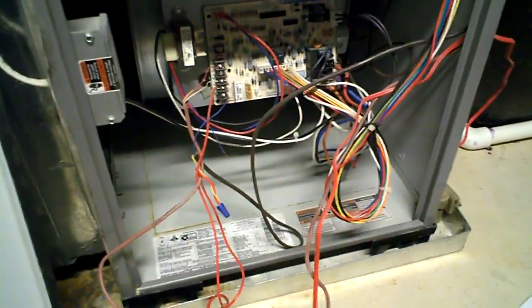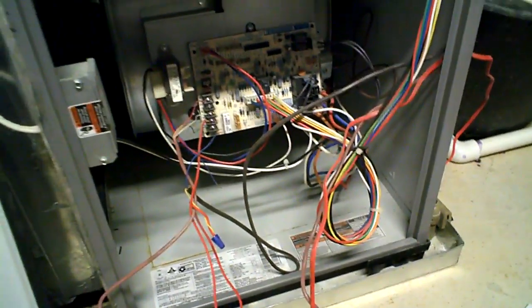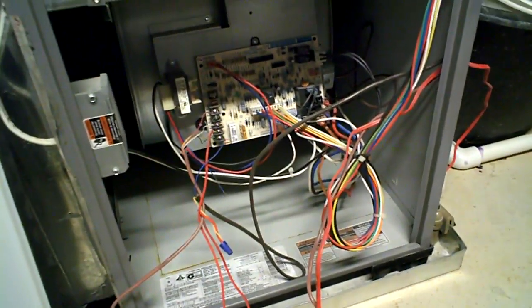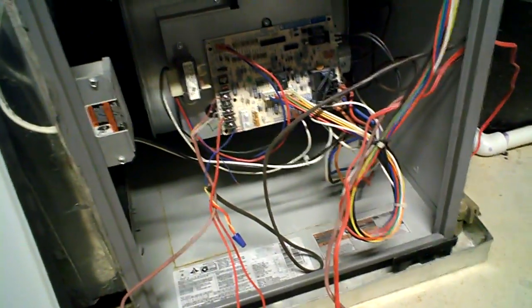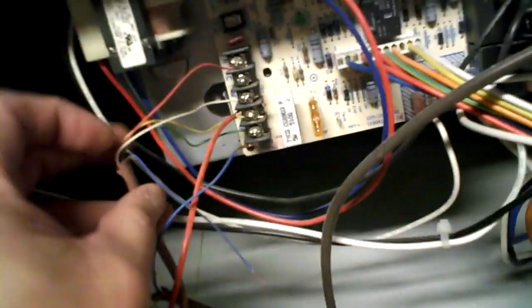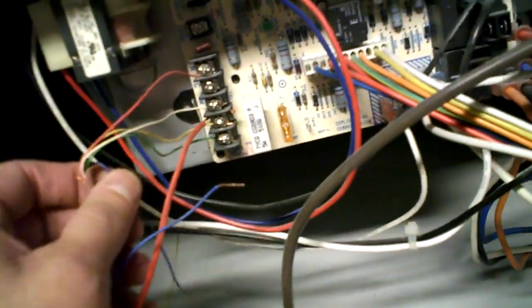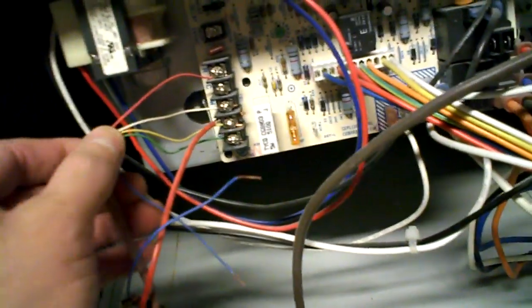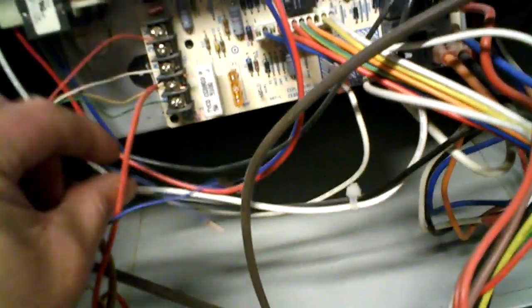Okay, I've discovered something on my system, since it's a very new system, about 3 years old, that may be of interest to people. In fact, it changes everything, because I'm not going to be installing this power extender, at least not right now, to see if this other idea works. As you can see here, and you may want to look at yours, I have like six or eight wires in this thermostat wire going up there, and I have a blue wire, and you need the blue or the common wire up there, so you need five wires at your thermostat.